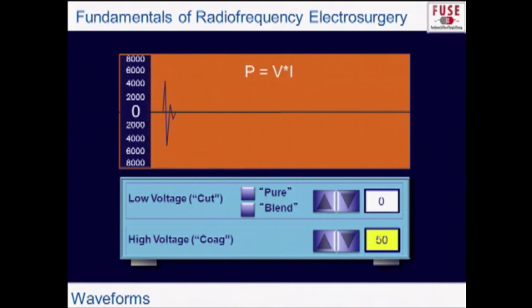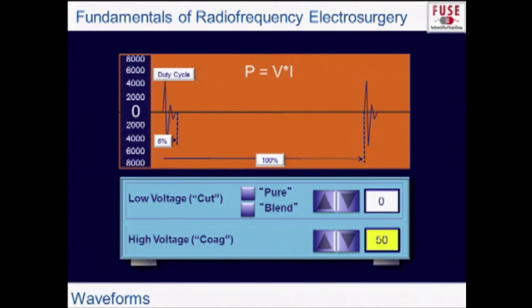The so-called coagulation output is very different — it has a very short duty cycle, only on about 6% of the time in a typical output. Because current is so reduced, voltage must be pushed very high. The key difference between coagulation and cutting at the same wattage is voltage: coagulation output has much higher voltage. This has important implications for pacemaker interference, capacitive coupling risks, and damage to insulation on your instruments.